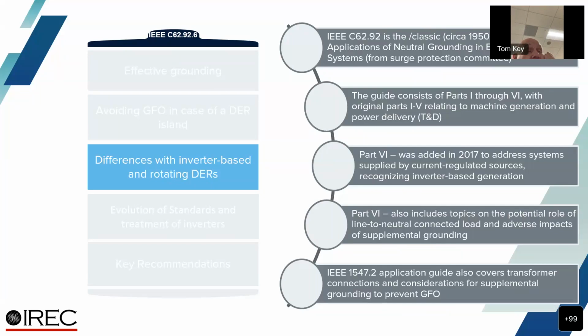But basically, the inverter is not as such a strong source as a synchronous machine, and so many times there's just enough, I'll call it incidental grounding in a power system. You get a line to ground connected load, and it has a similar effect to the grounding transformer. It holds down that line to neutral voltage on the unfaulted phases. So we came up with some rules of thumb that said if you have like 30% line to neutral connected load, inverters will work fine. You don't need supplemental grounding. If you installed a synchronous machine as a DER, then you would need it. That's well explained now in the bottom description there, the 1547.2, which, Brian, it's not out yet, right?